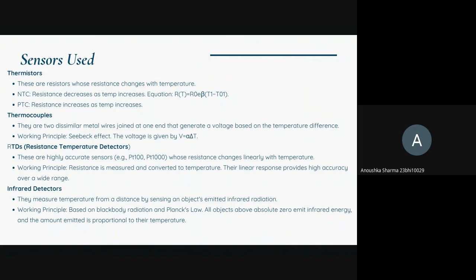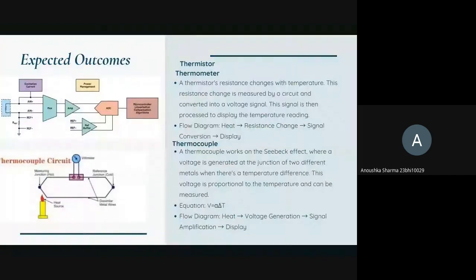Moving on to the next slide, we have the working principle of the thermistor thermometer and the thermocouple thermometer. First of all, we will look at the thermistor thermometer. The core principle is that a special material's electrical resistance changes in response to the temperature. This change in resistance is then converted into a small electrical signal, which is a voltage, by a circuit. This signal is then amplified and processed to be displayed. Then we come to the thermocouple. This device works based on the Seebeck effect. When two different metals are joined together, a temperature difference between the junctions creates a small voltage. This voltage is directly proportional to the temperature difference.